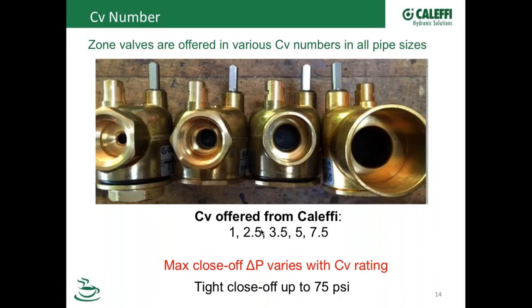All right, the CV number, I'll talk a little bit more about that. So here's an example. I just put these on my workbench and took a picture of them. And here's four of our different Z1 bodies. So notice the difference in these bodies. In fact, I think some of these are all three-quarter. It looks like an inverted flare there, a threaded type there, a sweat there, another sweat here. And notice the difference in these valves. And we offer 1, 2.5, 3.5, 5, and 7.5 CV rating on these valves.